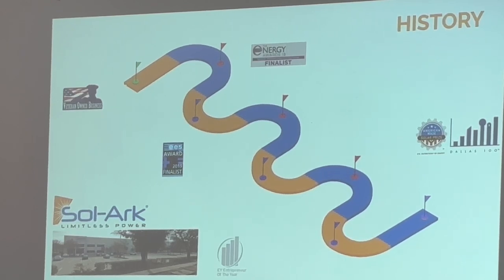For another example, you've got a big Enphase system on your roof. I've got some slides from an Enphase IQ8 install we did in Florida, where they wanted batteries, so we bring that Enphase system in through the AC port on the Sol-Ark, the smart loads port, and just AC couple that Enphase to DC coupled batteries. So this inverter will work with almost any circumstance with a retrofit - the solar's already on the roof, but you want to add a battery system, you can use this one.